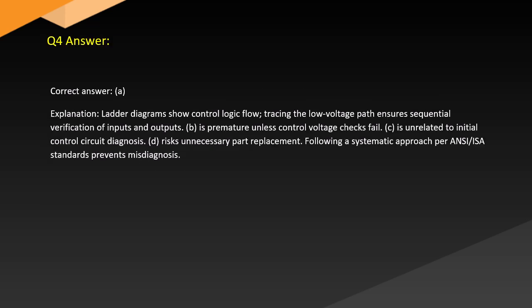Answer. Correct answer: A. Explanation. Ladder diagrams show control logic flow. Tracing the low voltage path ensures sequential verification of inputs and outputs. B is premature unless control voltage checks fail. C is unrelated to initial control circuit diagnosis. D risks unnecessary part replacement. Following a systematic approach per ANSI standards prevents misdiagnosis.